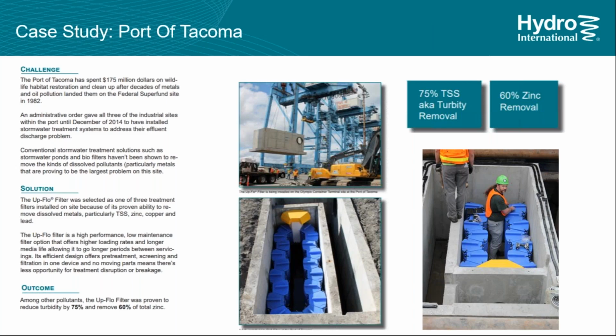The Port of Tacoma did not have to meet, say, Washington DOE regulations, so they got to choose whatever device they thought was best, as long as it got results that would keep them from being fined. They chose the CPZ mix based on the turbidity and the high concentration of zinc they saw on site, and it would do a great job of addressing metals.